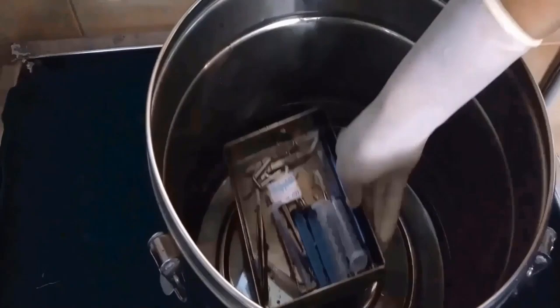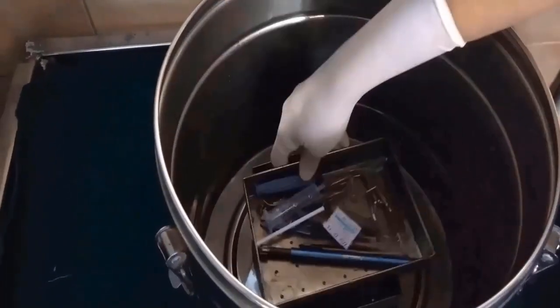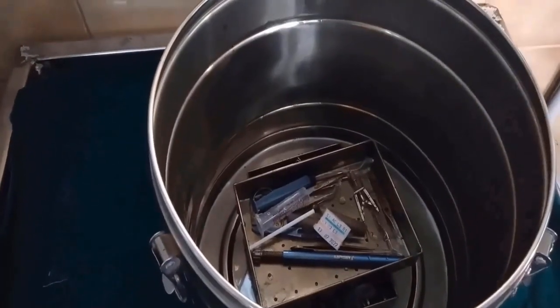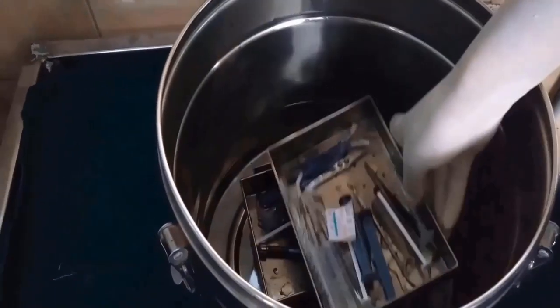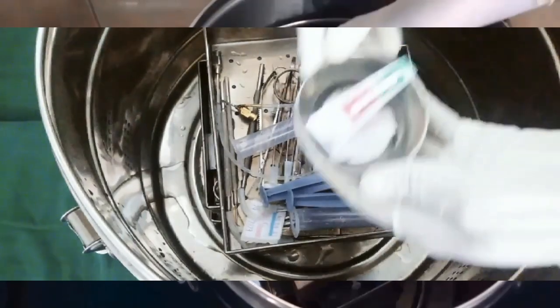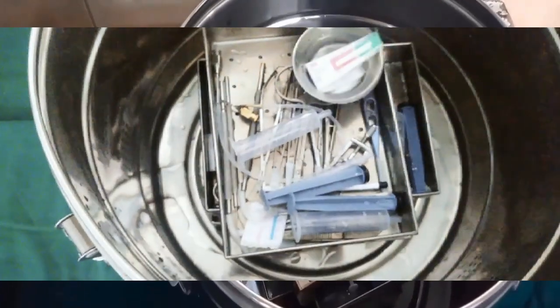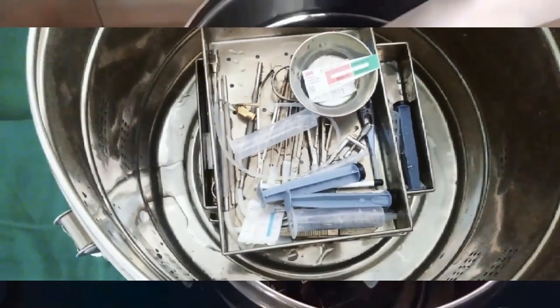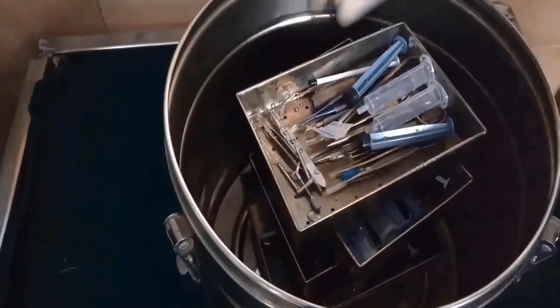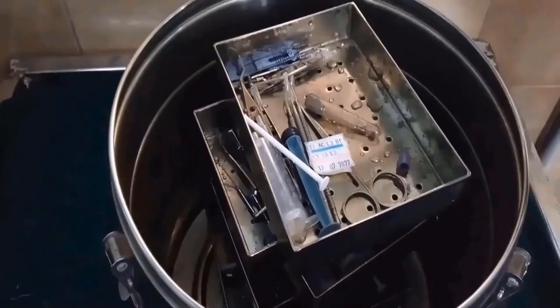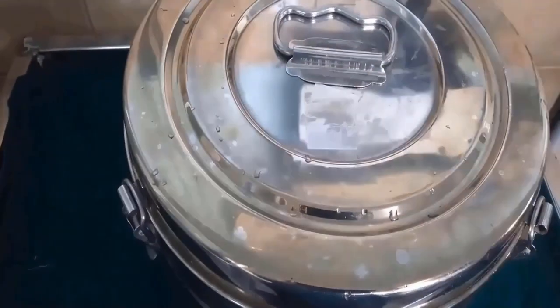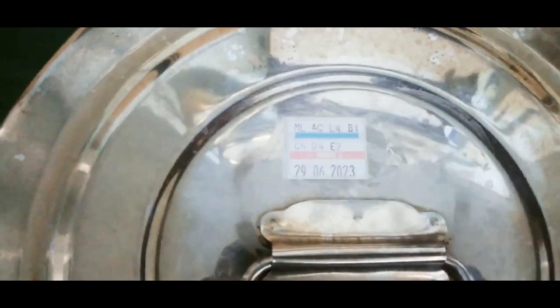Then the washed instrument set should be kept in a bin in perpendicular alignment and keep the class 1 indicator in each tray. That indicator should contain autoclave name, sister name, sterile date, expiry date and the load number. Check all and close the bin. Then keep class 1 and class 5 indicator in each bin.